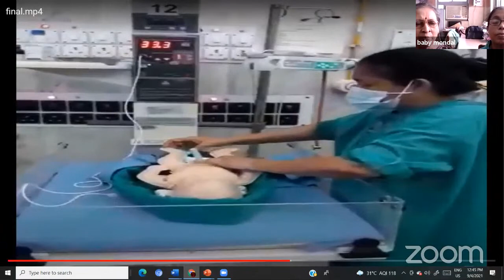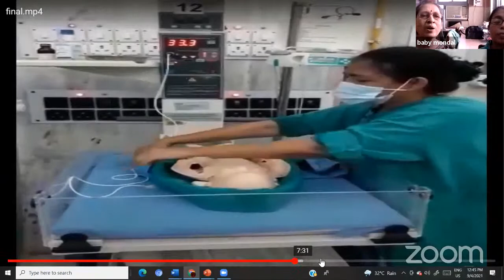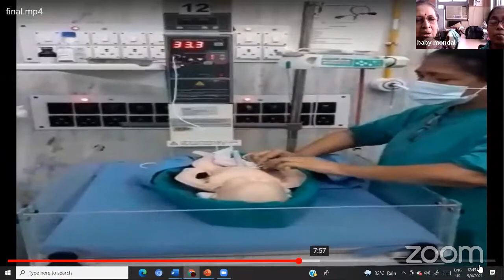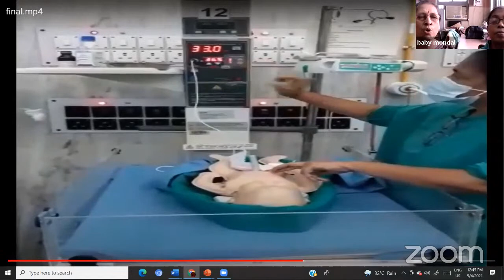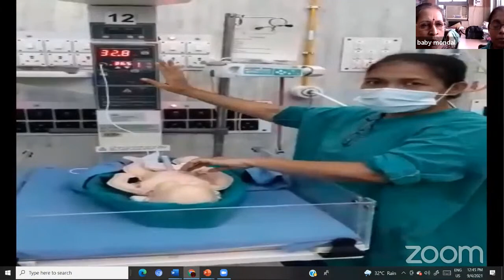Here, the baby is taken from the delivery room and handed over. The nursing staff is receiving the baby; at that time the warmer was in manual mode, and the probe was already cleaned. That probe was attached on the right upper abdomen, mainly the right hypochondriac region, and the warmer was changed from manual mode to servo control mode, and the set temperature was 36.5.